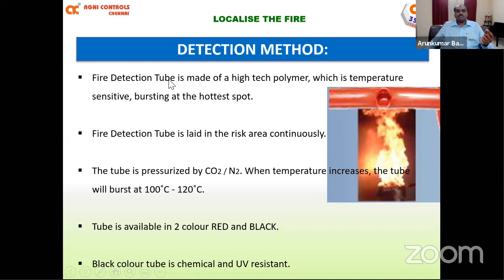It is nothing but a small polymer - a red colored tube, but a very temperature sensitive one. When a hotspot develops and the heat reaches around 100 to 120 degrees centigrade, this tube will burst. It's like a heat sensitive tube, and we use this particular tube inside our risk area, which can be an electrical panel in our case.